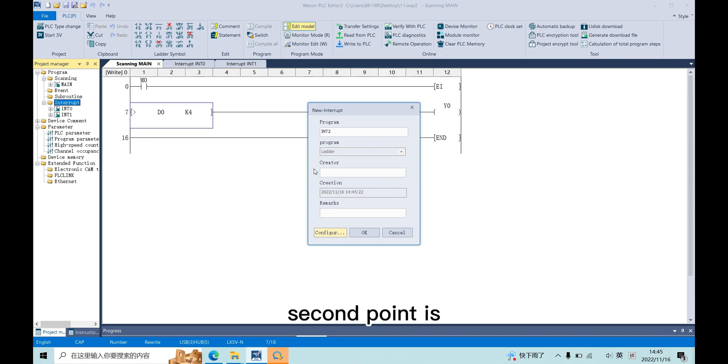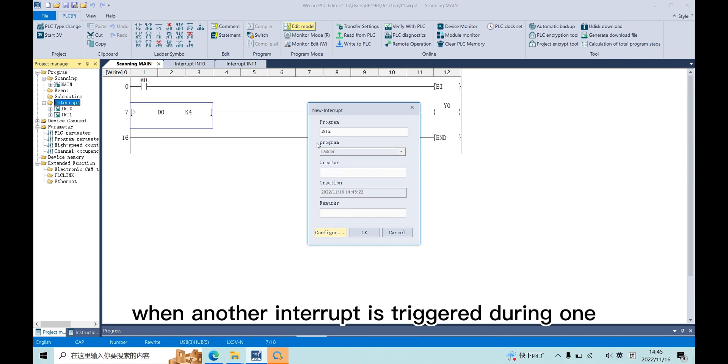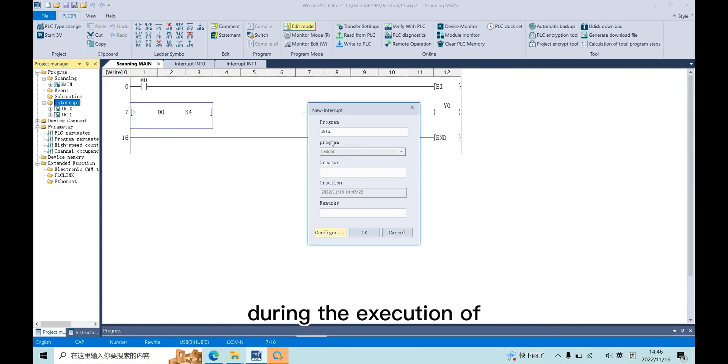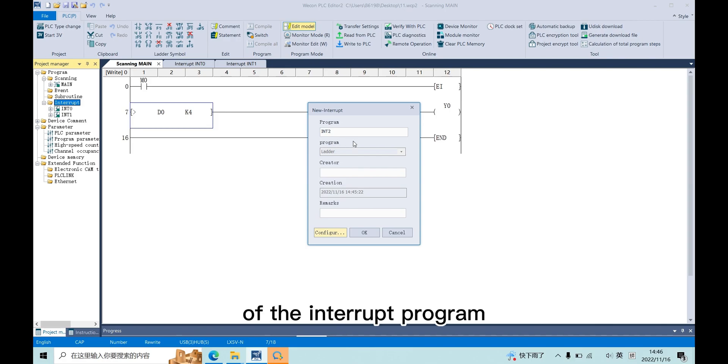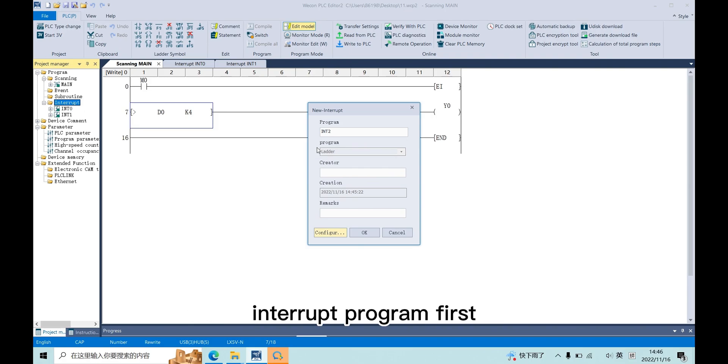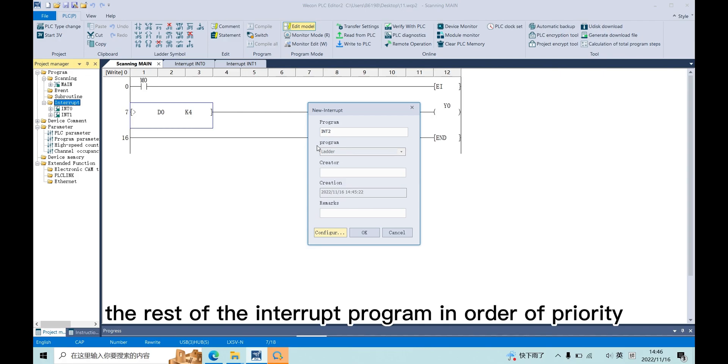Second point is when another interrupt is triggered during the execution of the interrupt program, the PLC will finish executing the current interrupt program first and then process the rest of the interrupt program in order of priority.